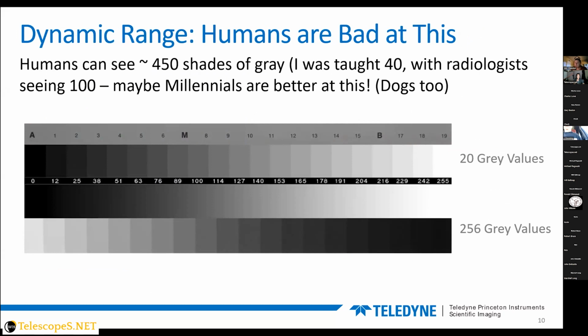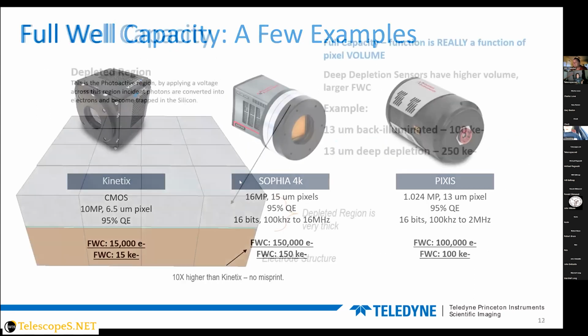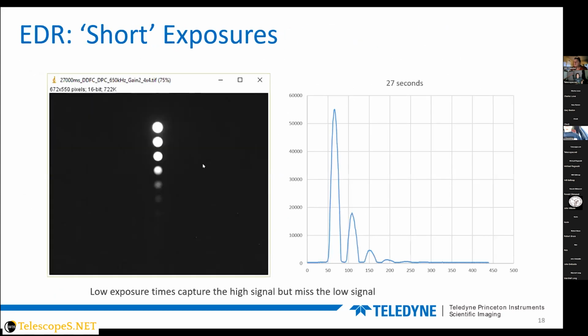You can actually image it, measure the values, and validate what the EDR is doing, just to be sure that you're right, because there's a number of ways to do it. So if it was me, I would want to validate it. This is kind of the simplest method of validating that. The method I show later using a tritium source on a black background is just as easy to validate with, but these tritium sources are not easy to come by, whereas the plastic strip of gray values is very easy to come by.